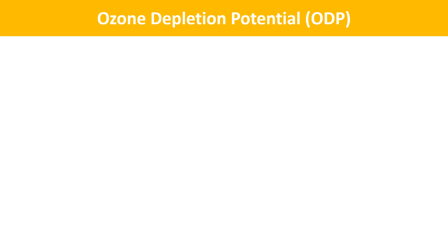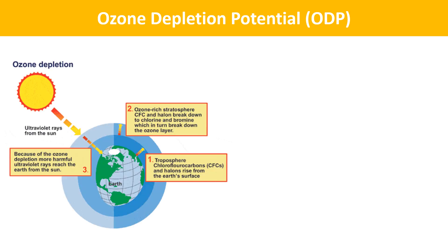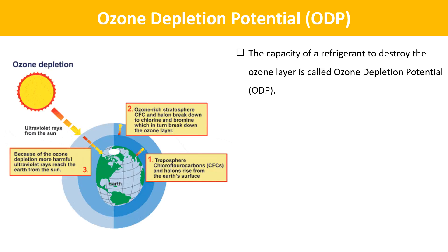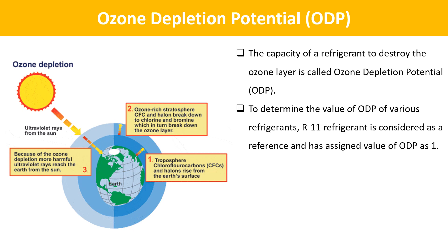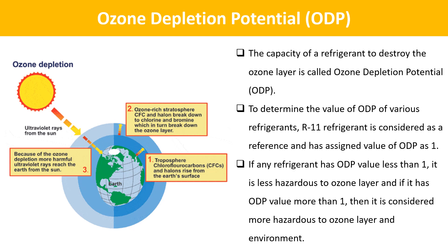The next term is Ozone Depletion Potential. The capacity of a refrigerant to destroy the ozone layer is called ozone depletion potential. To determine the ODP value of various refrigerants, R11 refrigerant is considered as a reference and has an ODP value of 1. If any refrigerant has an ODP value less than 1, it is less hazardous to the ozone layer; if it has an ODP value more than 1, it is considered more hazardous to the ozone layer and environment.